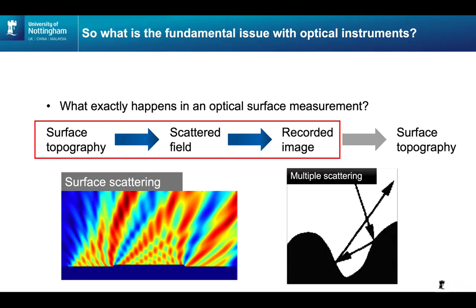So let's just go back to the standards infrastructure that is in place for optical, for at least contact coordinate measurement systems. So the ISO 10360 series, very well known series of standards that covers performance verification of CMS, and there is a part on optical coordinate measurement. Well, there is a part 8 in fact which covers point scanning systems, and then fringe projection and those types of systems, so point cloud type systems, will be covered in part 13, which is under review at the moment. But it's not calibration. It's about performance verification. So it's about giving users the tests they need to say that the instrument is doing what it says in its specifications.